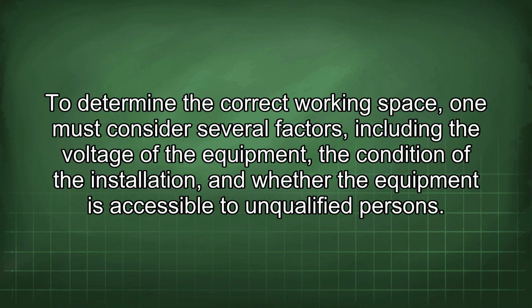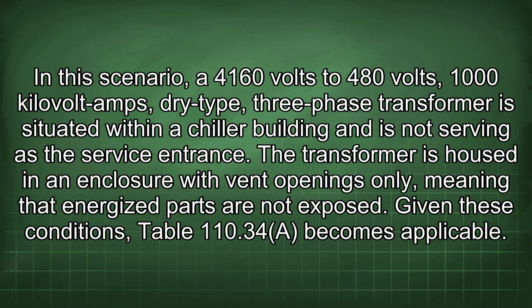To determine the correct working space, one must consider several factors, including the voltage of the equipment, the condition of the installation, and whether the equipment is accessible to unqualified persons. In this scenario, a 4160 volts to 480 volts, 1000 kilovolt amps, dry type, three-phase transformer is situated within a chiller building and is not serving as the service entrance. The transformer is housed in an enclosure with vent openings only, meaning that energized parts are not exposed. Given these conditions, Table 110.34 becomes applicable.